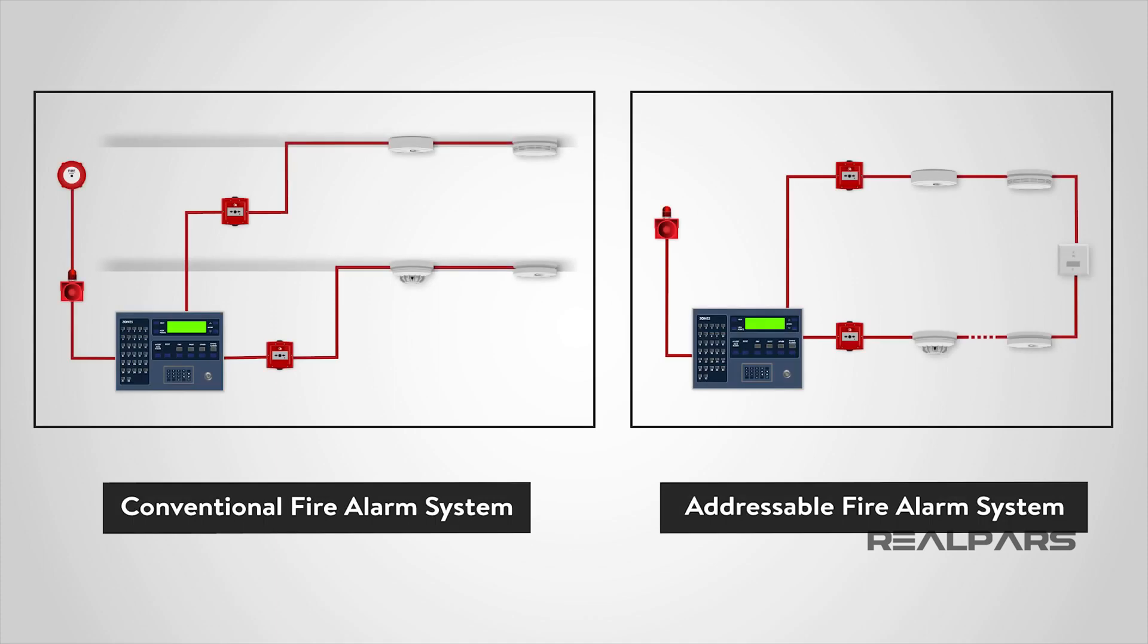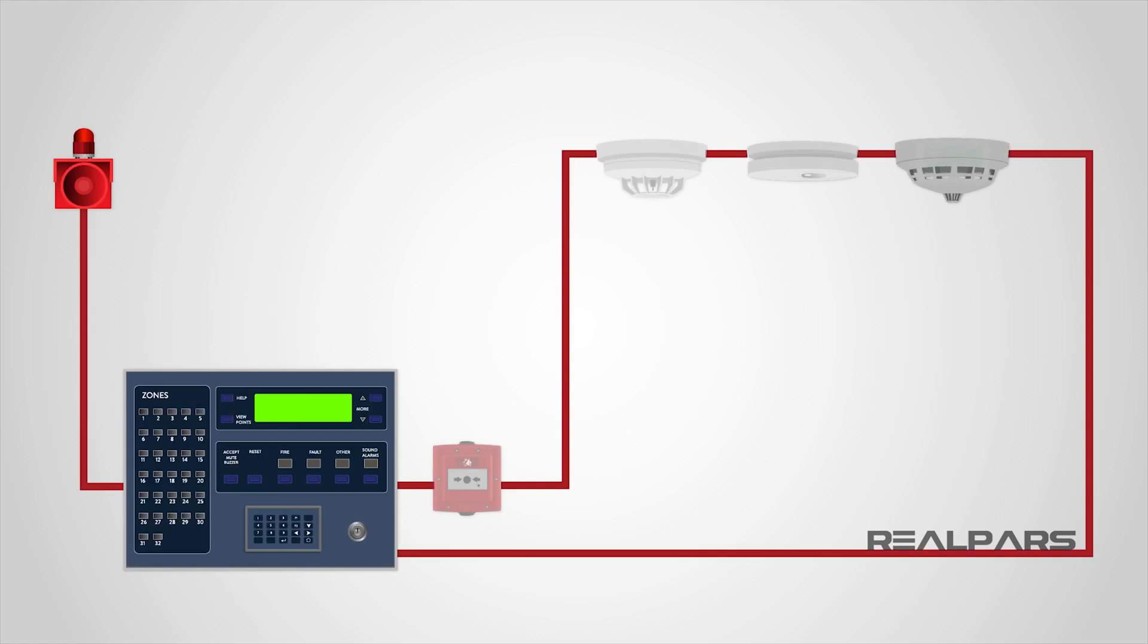In the previous two systems, the conventional system and the addressable system, the detectors are not considered intelligent as they can only give output signals representing the value of detected phenomena. It is left up to the control unit to decide whether there is a fire, fault, pre-alarm, or other. However, in our next type of system, which is an intelligent fire alarm system, each detector effectively incorporates its own computer.